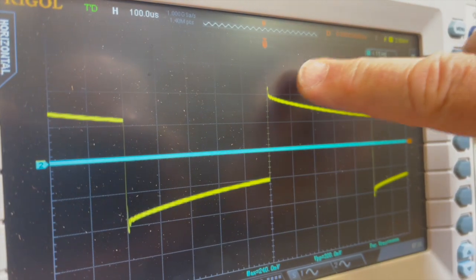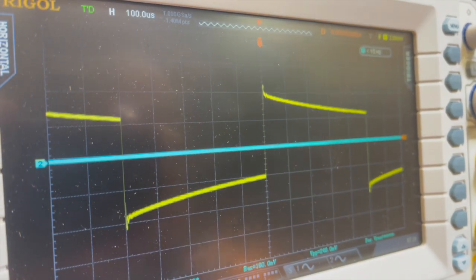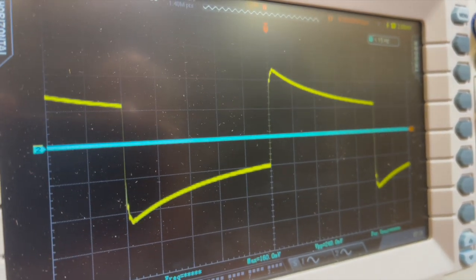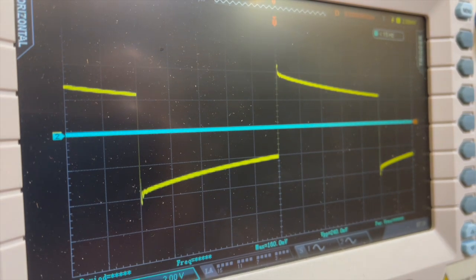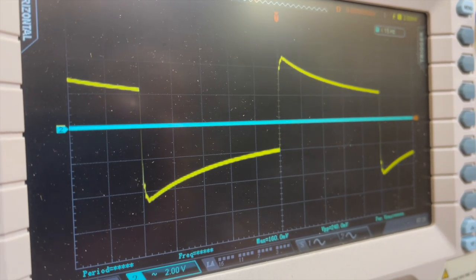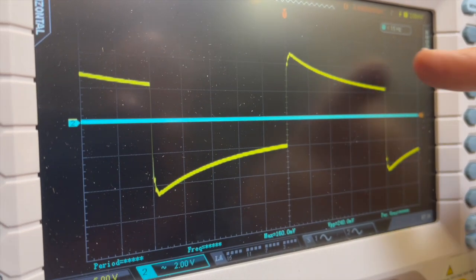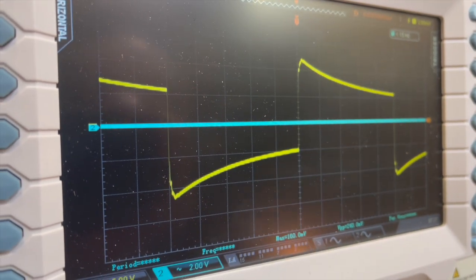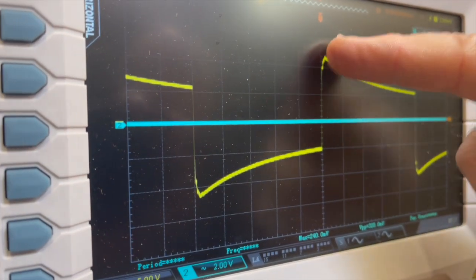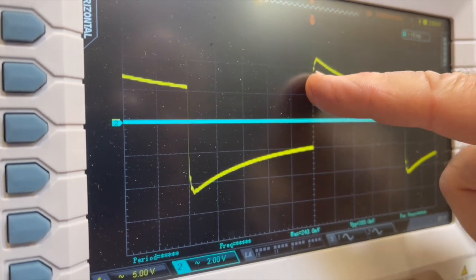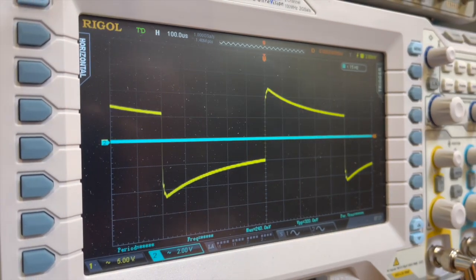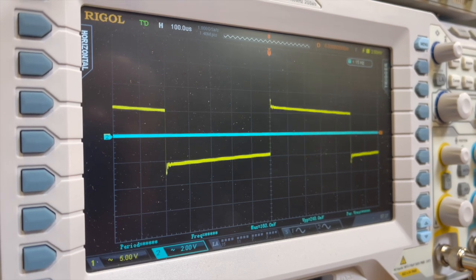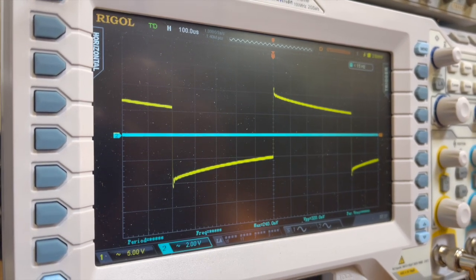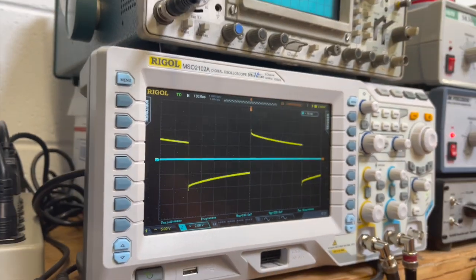You see this? It's a little inverted, though. A teeny little peak. Yeah, but that's a peak. See, it isn't moving. It's just that in a bright mode, the frequency shift caused by the reactive load is overtaking that little anomaly there, and that anomaly is called ringing. That's the transformer oscillating at a very high frequency at a very small amount.